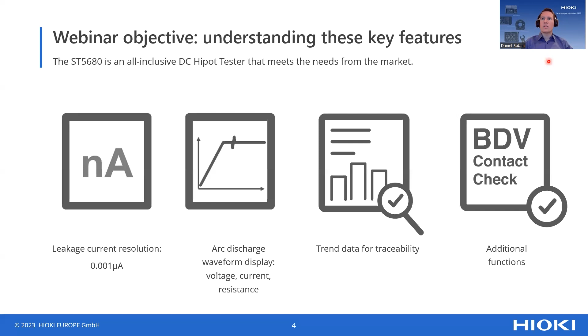Out of this webinar, we hope you will understand three main features. The DC Hipot Tester has three main USPs which make it an all-inclusive Hipot Tester, especially for the battery industry: a higher current resolution compared to our existing range, the ability to understand arc discharges of battery packs, and trend data storage that can be used for traceability purposes. These are the main features we should focus on with customers. Additional features like a breakdown voltage test function or a contact check function will also be shown briefly.